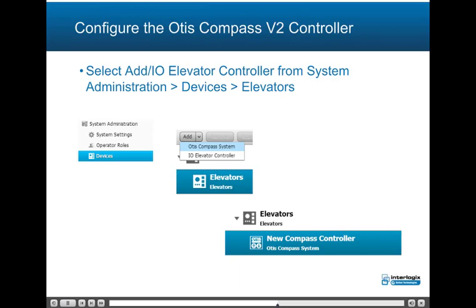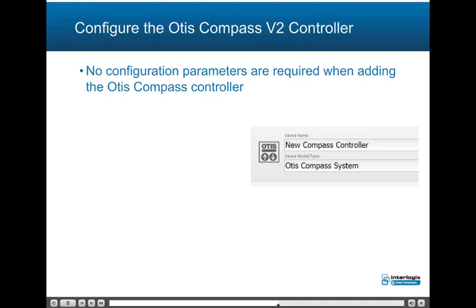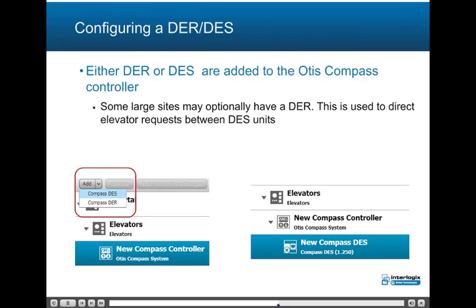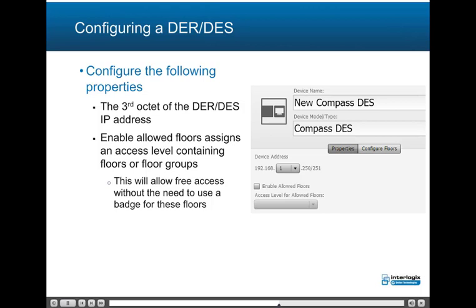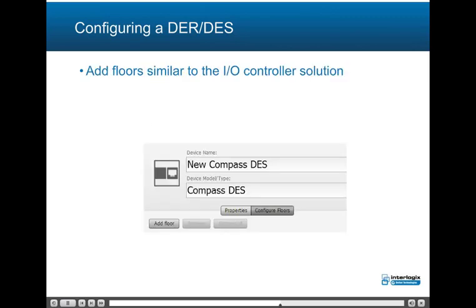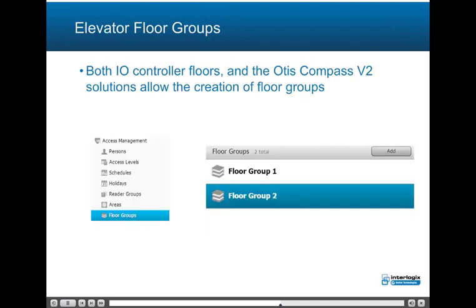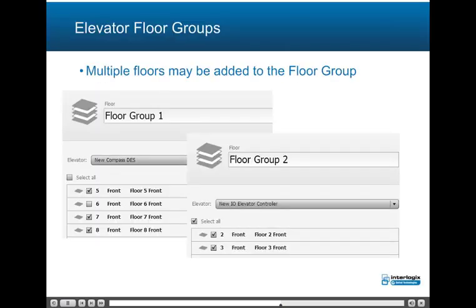To configure the Otis Compass V2 controller, from System Administration select Devices, then Elevators, then add an I.O. Elevator controller. No additional configuration parameters are required when adding the Otis Compass controller. Next, either a DER or DES is added to the Otis Compass controller. The following properties will need to be configured: the third octet of the DER/DES IP address; optionally enable allowed floors — this configuration assigns an access level containing floors or floor groups to allow free access to specific floors during specific times without the need to use a badge (sometimes referred to as day mode). Multiple floors may be added to the floor group. Either individual floors or floor groups may be assigned to the access level, which is then assigned to a badge.